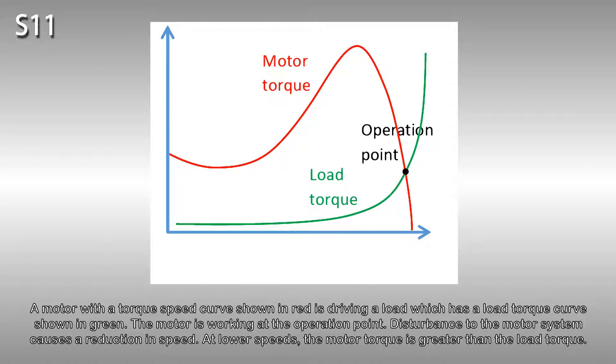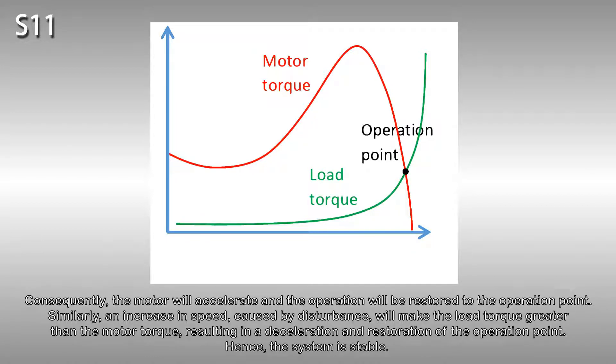Consequently, the motor will accelerate and the operation will be restored to the operation point. Similarly, an increase in speed caused by disturbance will make the load torque greater than the motor torque, resulting in a deceleration and restoration of the operation point. Hence, the system is stable.